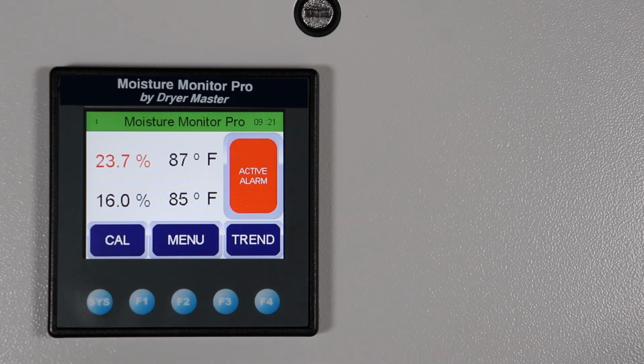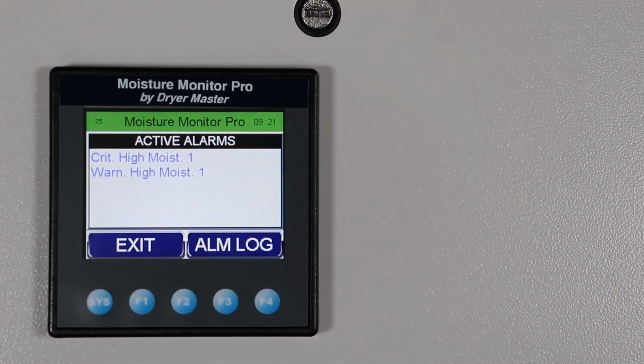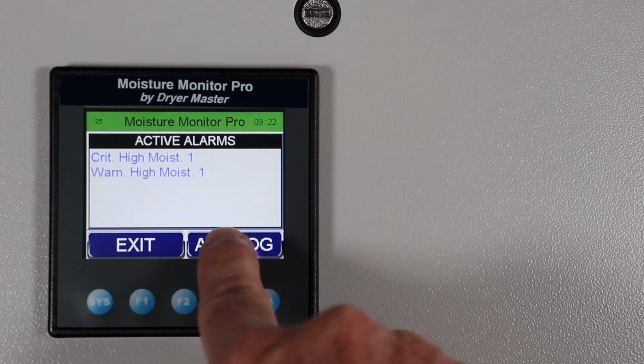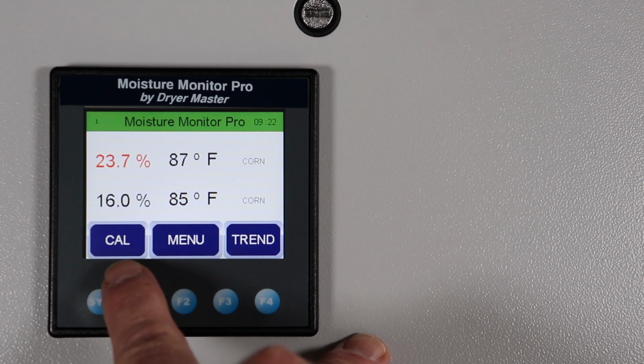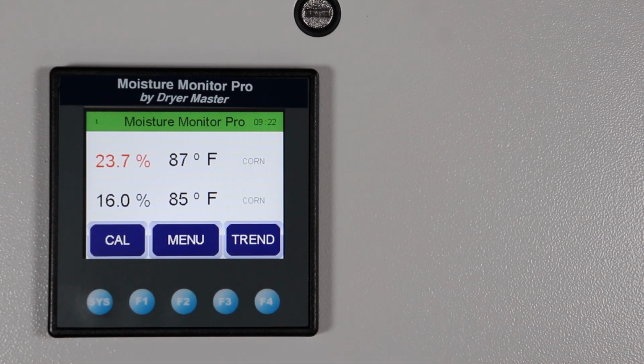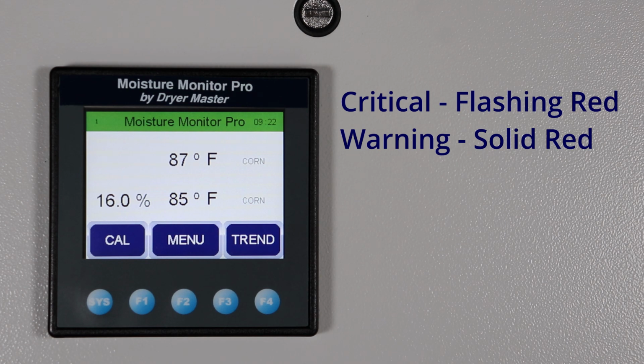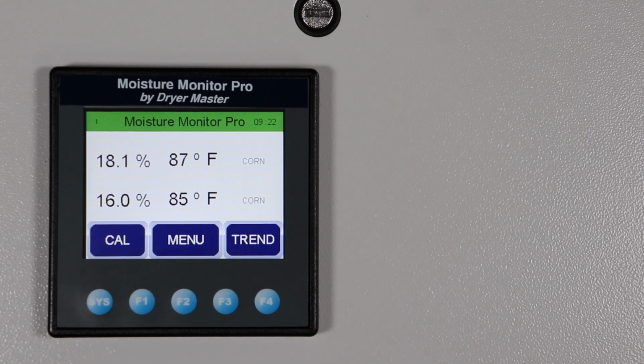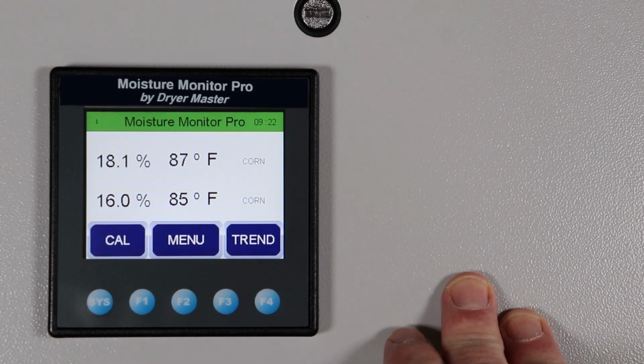And if there's an active alarm, you can acknowledge it by hitting the active alarm button. It'll list you the active alarms. So we've got a warning high and a critical high, obviously, because it's over the warning and the critical limit. If you want to see a log of alarms, just press that. And while it's still an alarm, if it's into a critical level, it'll flash. If it's a warning level, it'll just be a solid number. Okay, so if we take it to this, we should have a warning alarm after 10 seconds.